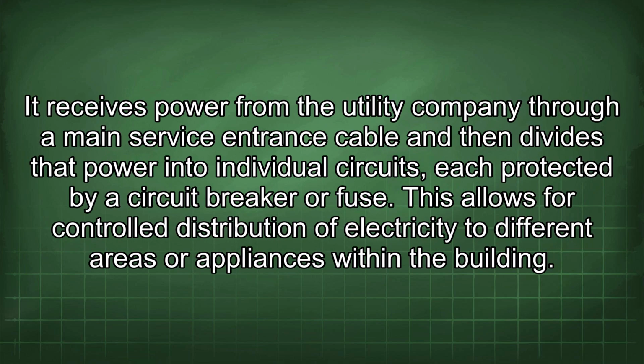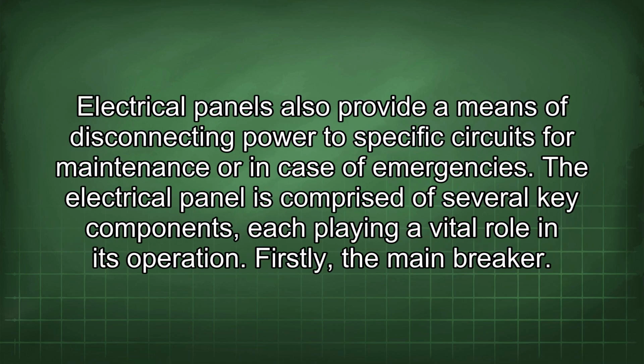It receives power from the utility company through a main service entrance cable and then divides that power into individual circuits, each protected by a circuit breaker or fuse. This allows for controlled distribution of electricity to different areas or appliances within the building. Electrical panels also provide a means of disconnecting power to specific circuits for maintenance or in case of emergencies. The electrical panel is comprised of several key components, each playing a vital role in its operation.